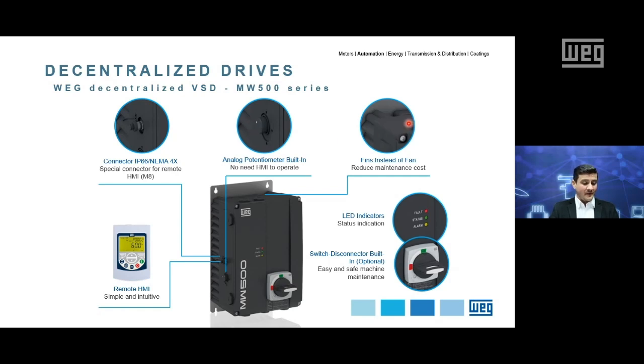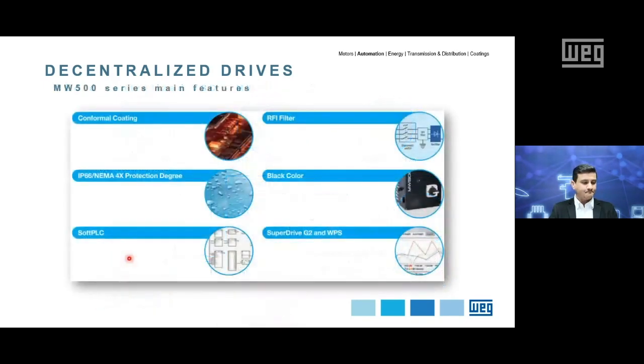It has fins instead of fans, which makes the inverter robust and suitable to operate within harsh environments and applications that include water and dust, and of course, avoiding downtime for maintenance, which means cost reduction again, if you don't need to use service calls. Further to this, the design allows the inverter to work up to 50 degrees in motor-mounted configuration. LED indication allows the user to check the status of the drive, and a switch disconnector can be offered as an option, which provides easy and safe machine maintenance, and a remote HMI can be offered as an option if required as well.